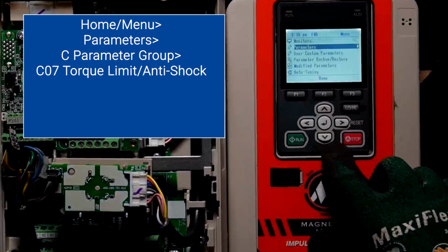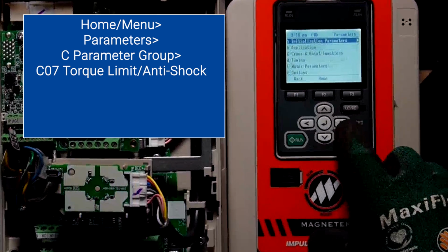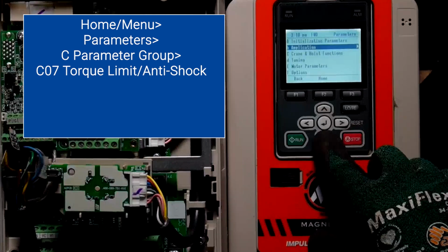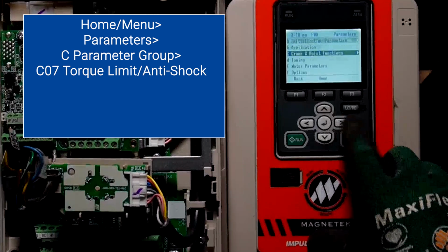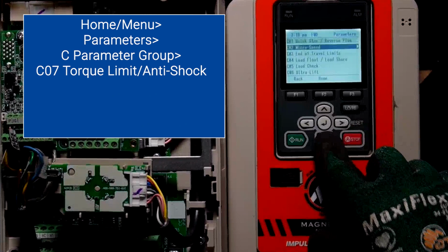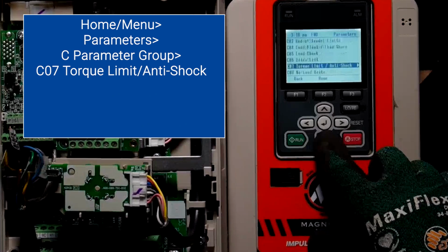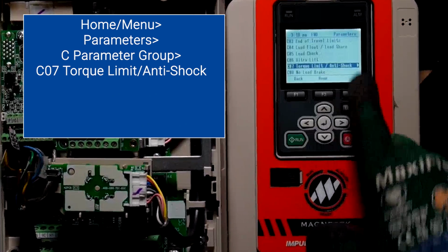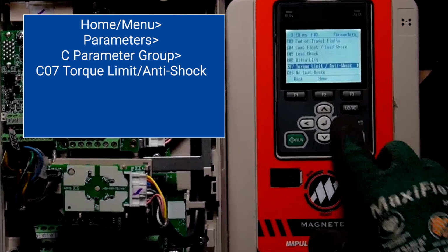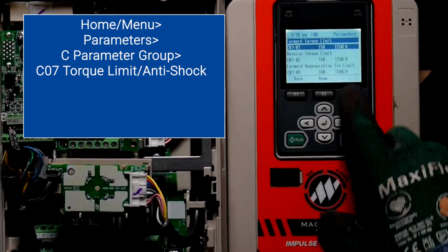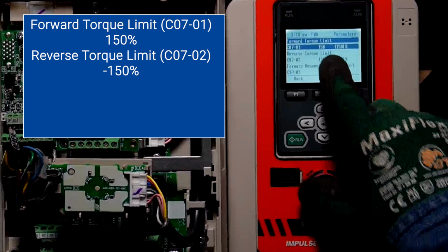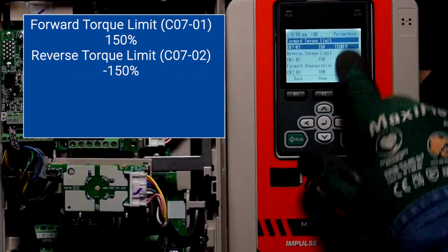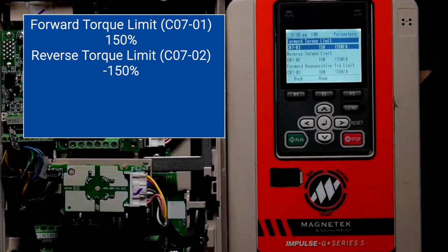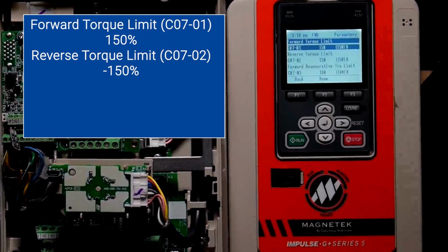We're going to go into the parameters. The torque limits are loaded in the group C parameters, and it's actually the C7s. So I'm going to scroll down. There's the C7 torque limit, as well as the anti-shock is loaded in there. And the reverse torque limit and forward torque limit are both set to 150%. This is the maximum amount of torque that the drive will allow itself to produce.